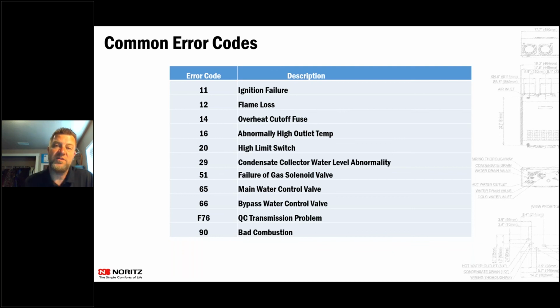If they haven't flushed the unit or taken care of the unit, that scale will let the unit get too hot and get that heat exchanger too hot to where it will overheat and throw those error codes. So if you ever had an older unit that's getting an abnormally high outlet temperature or an overheating cutoff fuse, that would be the reason. Also with that 16, if it's a water temperature outlet, then that would mean that the mixing valve that is supposed to temper that water has gone bad. So you would just need to replace that.